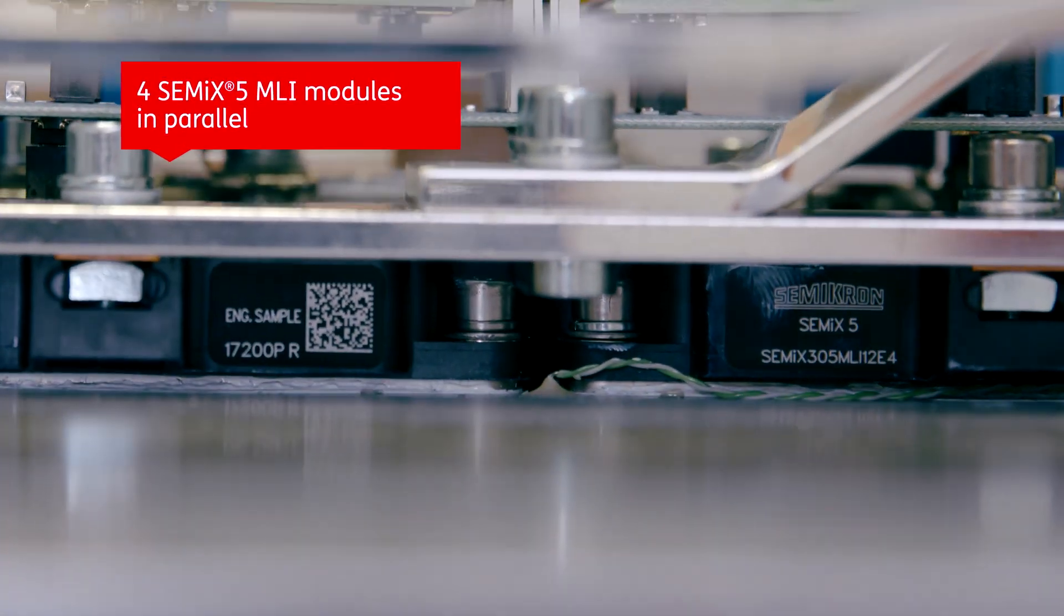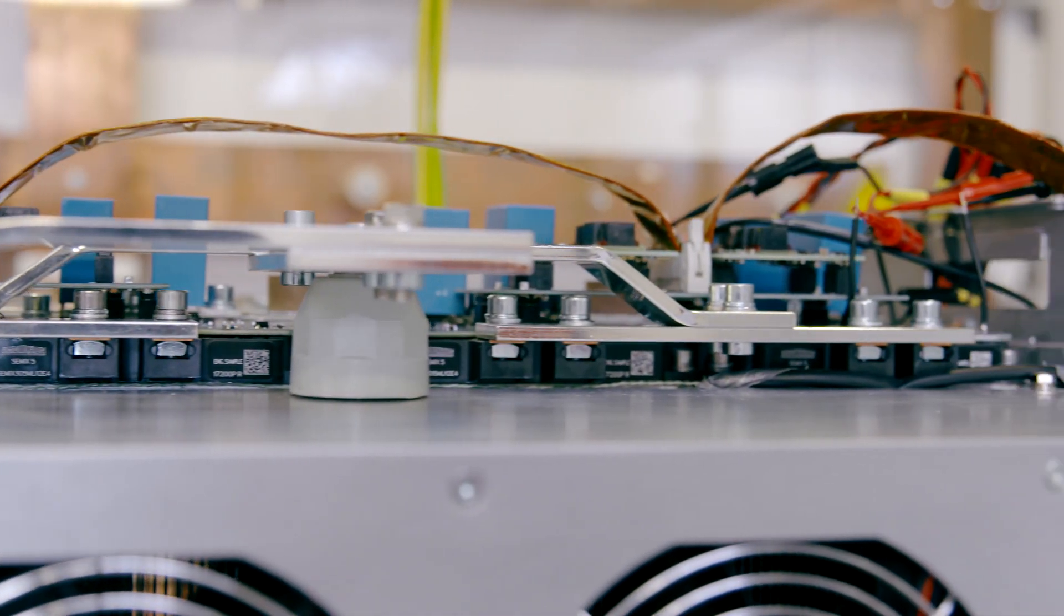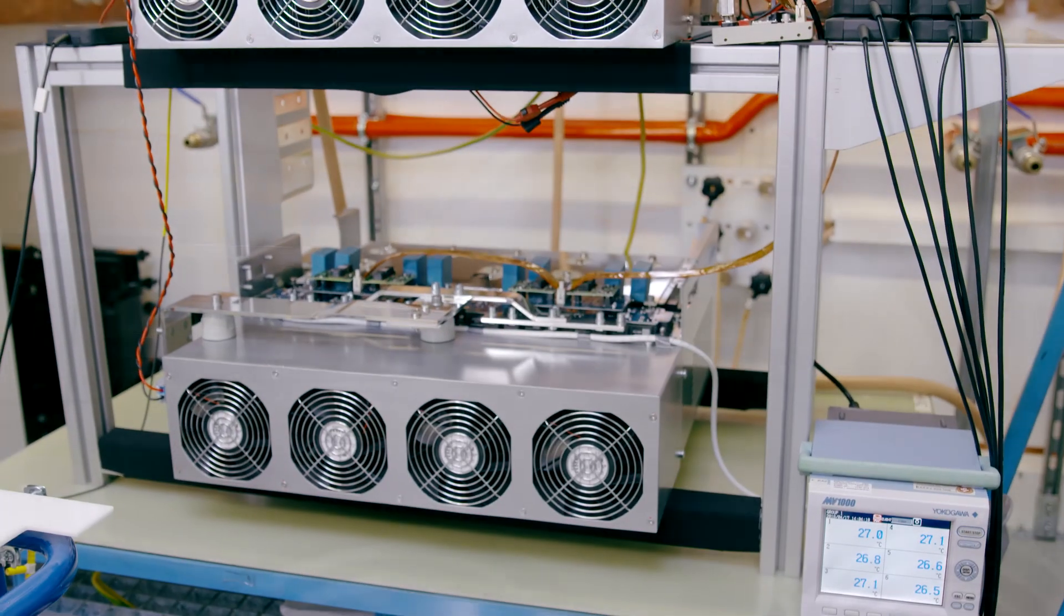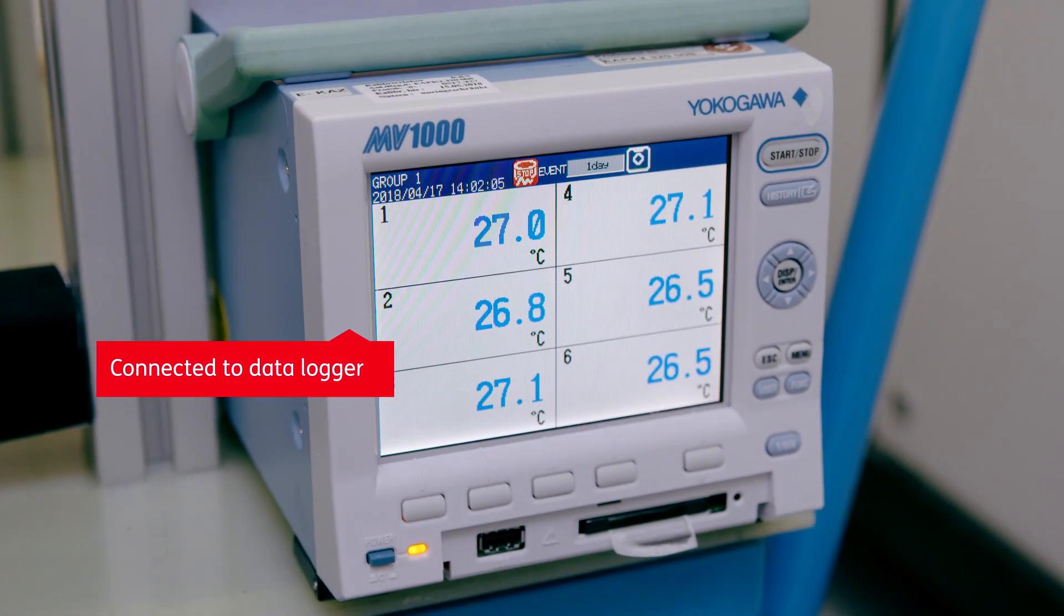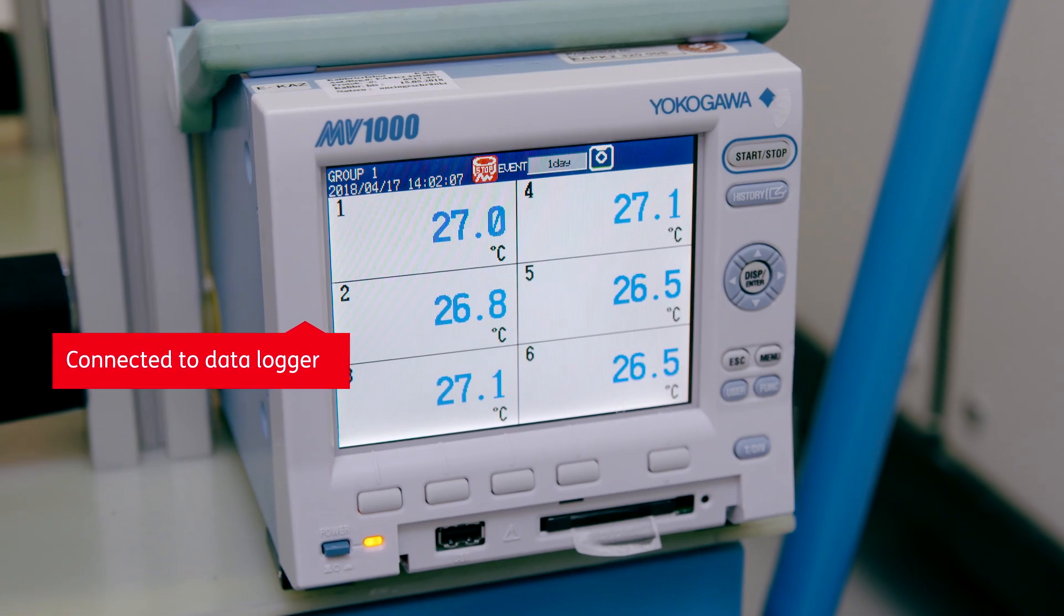One with a power factor of one, the other with a power factor of minus one. These tests enable us to monitor temperatures and operating conditions, as well as voltages and currents, meaning we can simulate and test the different conditions that will occur in the field.